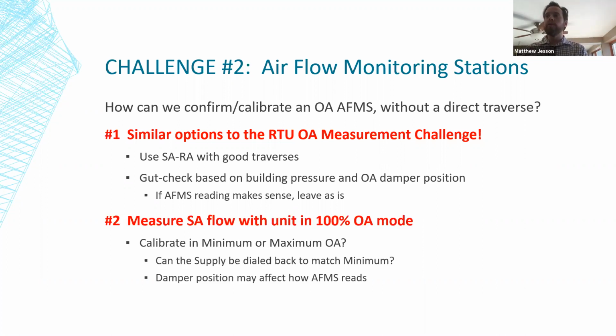Another option would be to measure the supply airflow with the unit running in 100% outdoor air mode. It can be a little bit tricky, and what you might have to think about is, do I want to calibrate or confirm this airflow station in minimum or maximum outdoor air mode? Airflow stations will typically read very well at whatever airflow they're calibrated at, and some have a 2-point calibration sequence that you can use. But for most of them, if you get to double the flow that it was calibrated at, or half the flow, it might read off by quite a bit.